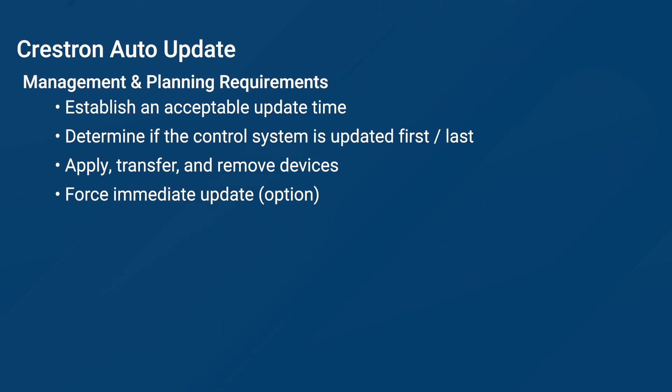You must also determine if you are updating the same control system running your Auto-Update. If you are using a control processor to update other devices, that processor must be updated first or last, as it is facilitating the update of the other devices.